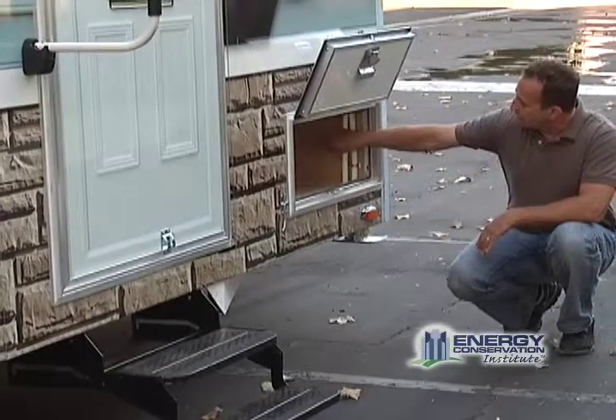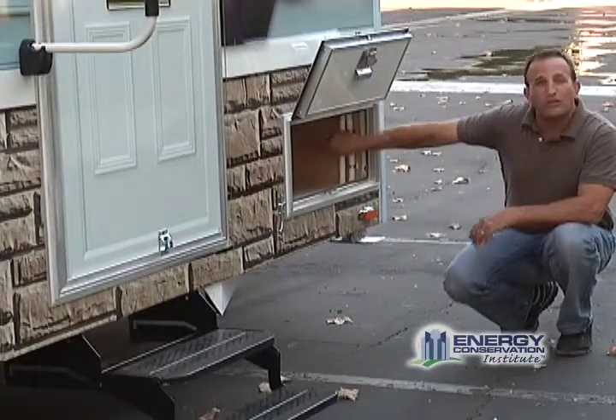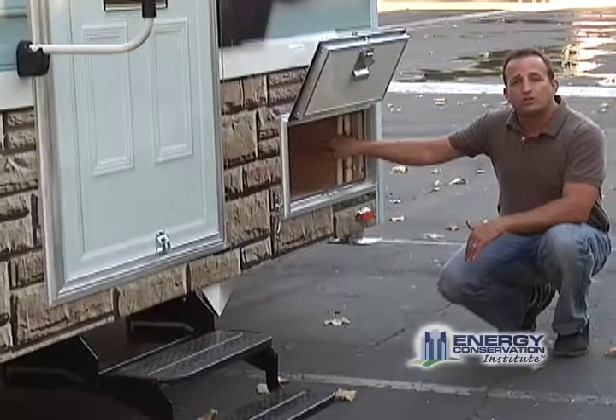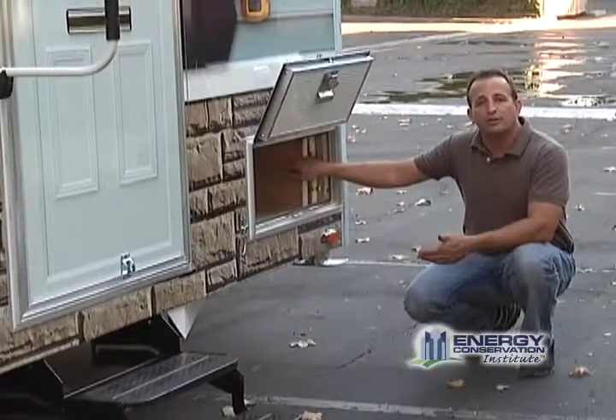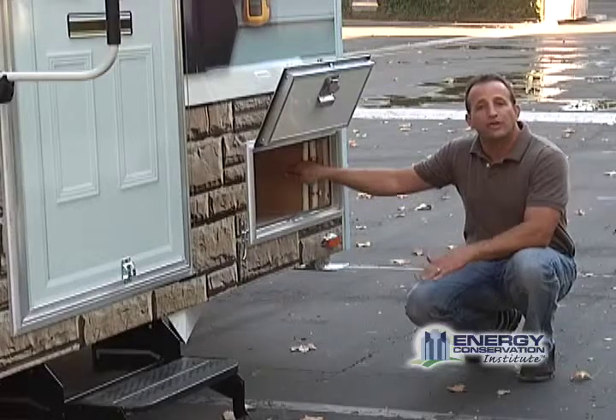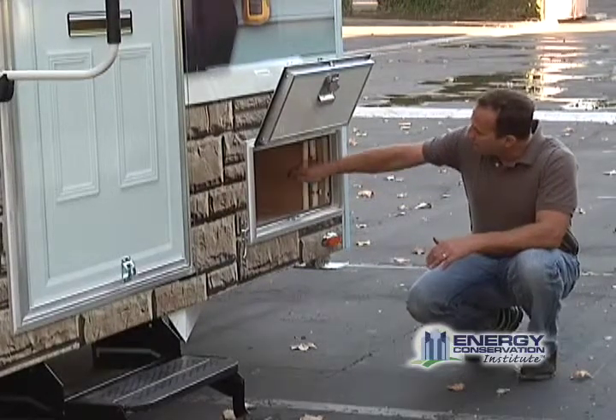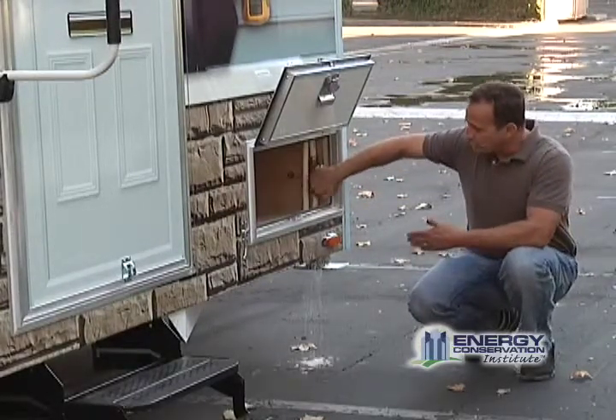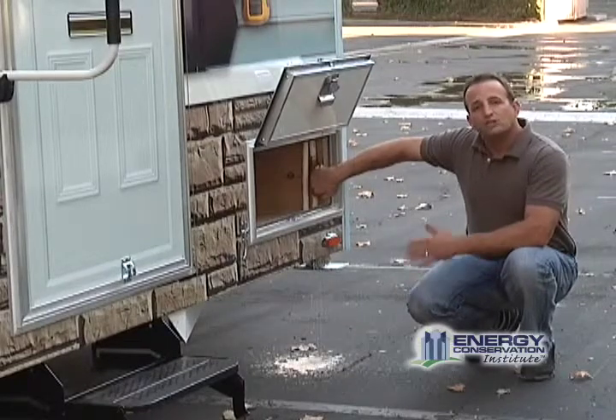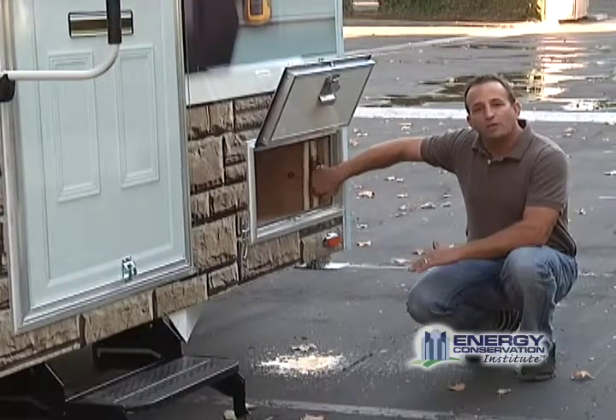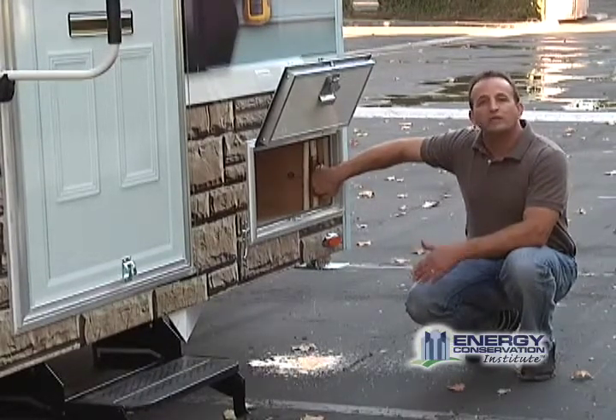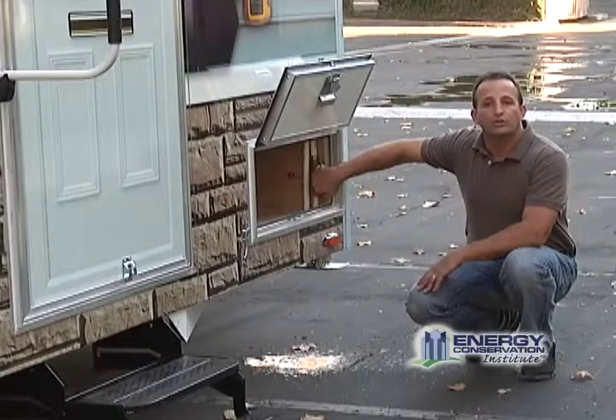It's also the valve we use to get rid of hot water from the heater. So if you're testing the water heater and heat the water to the point it won't fire anymore, just open this valve to release the water out. It's also a good idea to keep this valve open while filling the tank, so you don't inadvertently overfill it.